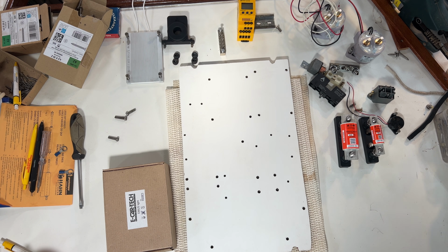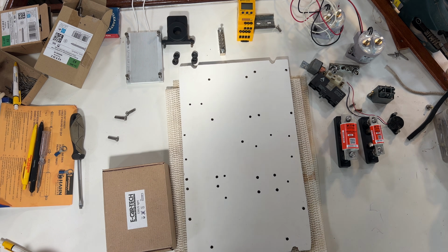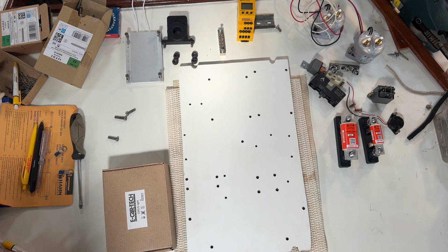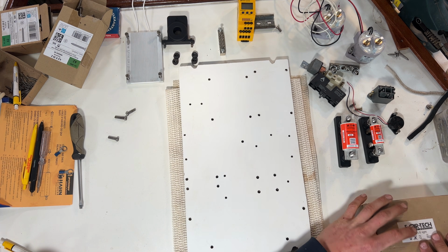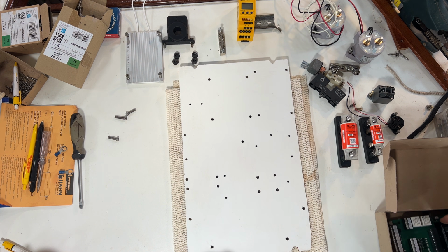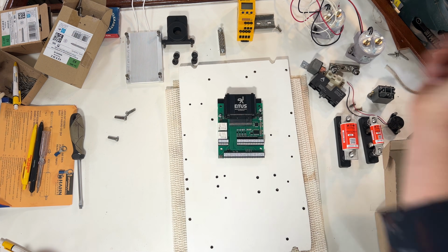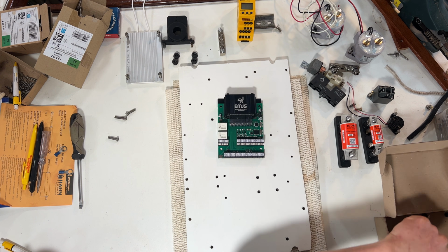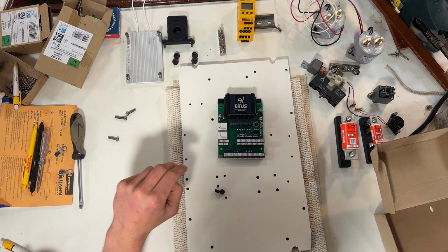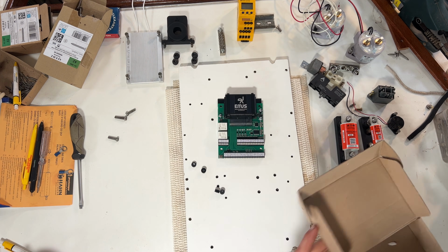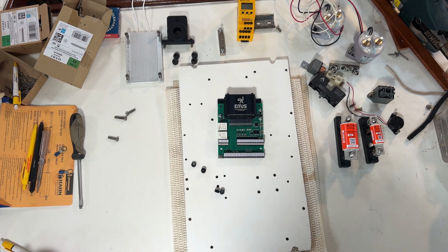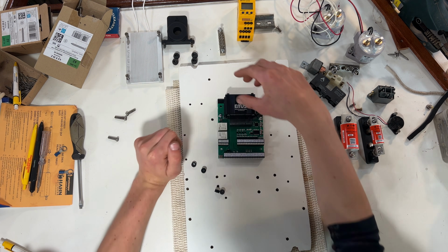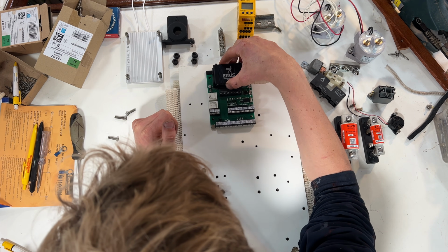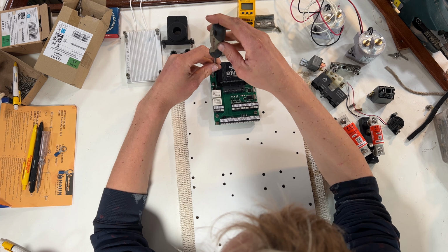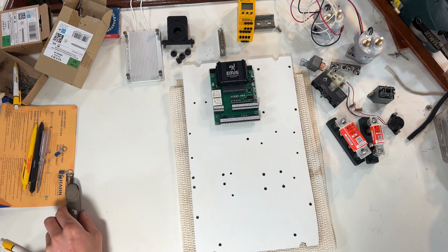The overall design, the component selection and the BMS configuration were all done by EV Europe, who are real experts in this field. They supplied the battery modules and the high voltage architecture, and we're building the system using their designs. First, the BMS. This is the actual brains of the battery. It receives data from all the cell sensors, temperature probes, current sensors, insulation monitor and the safety interlock switches, and it controls the contactors, the chargers, the alarms, everything.